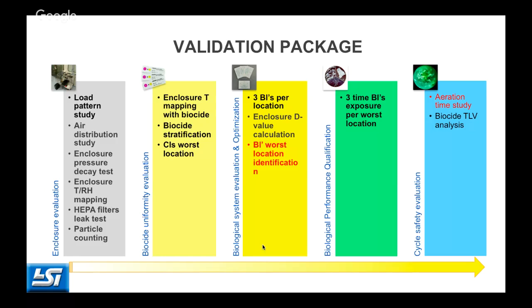After biocide uniformity, chemical, I would say, biocide uniformity, then we move to biological challenge. So we are working with 3 BIs per location. This is because we can make a statistic approach of the D value location by location with the 3 BIs. And this helps us also to make the calculation of the enclosure of the system, of our transfer hatch D value. So D value changes from one unit to the other unit, and we have to make the calculation for each single unit, and then the BI also can show us what is the worst location.